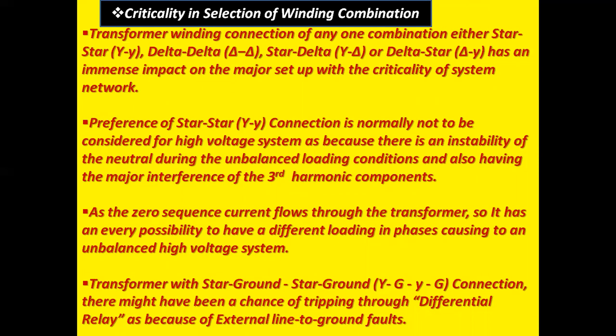because there is an instability of neutral during unbalanced loading conditions, and also a major interference of the third harmonic components. As the zero sequence current flows through the transformer, it has every possibility of different loading in phases, causing an unbalanced high voltage system.